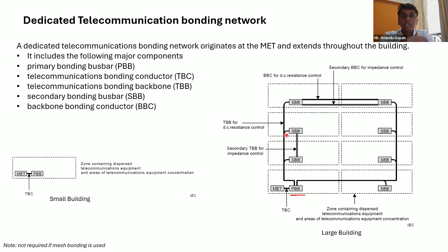and the structural metal at that location. Preferably you connect it to the structural metal also. Now the bus bar sizes of this PBB and SBB. PBB is primary bonding, so it is a little bit bigger. This is minimum 100 mm, and this is minimum 50 mm. The thickness is 6.35 mm, and the contact resistance when you are connecting to this bus bar must be less than 0.1 milliohms, 100 microohms again.